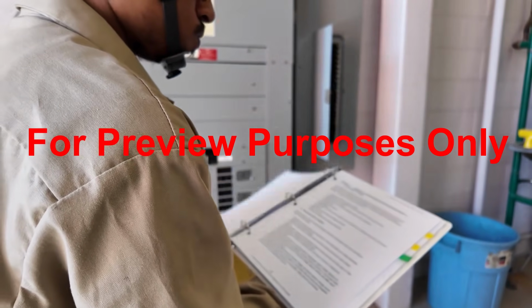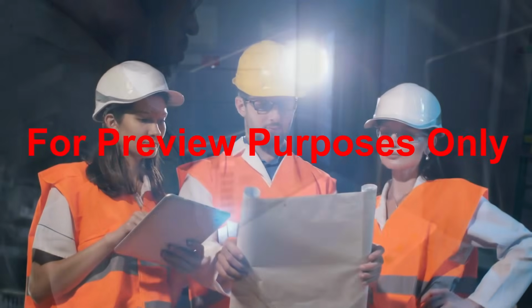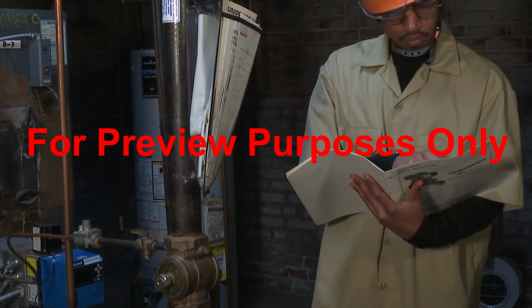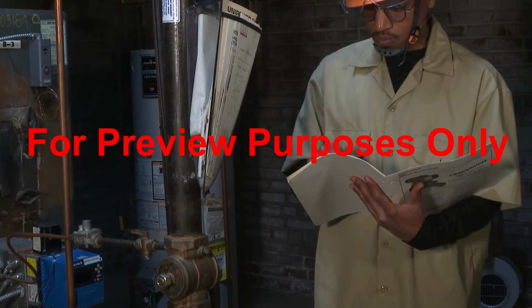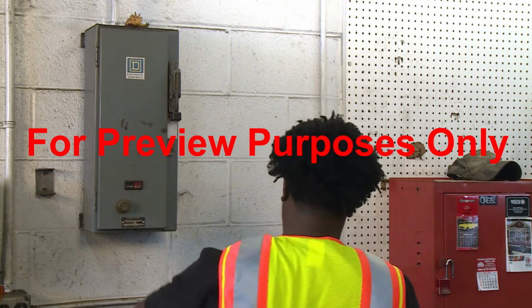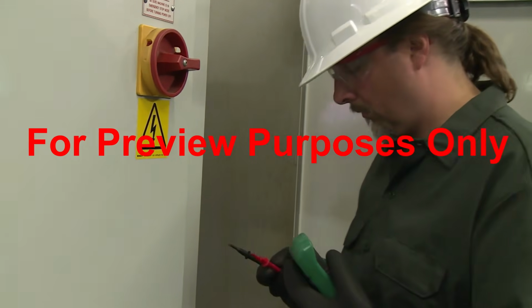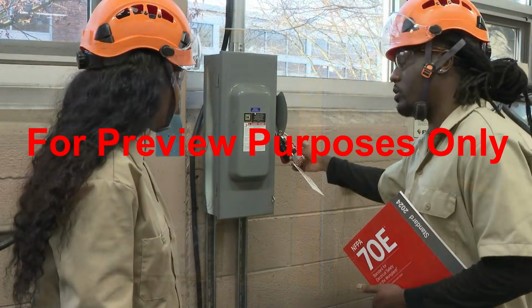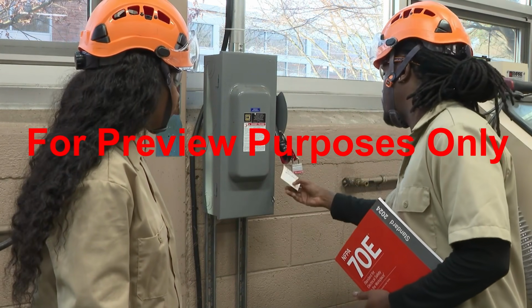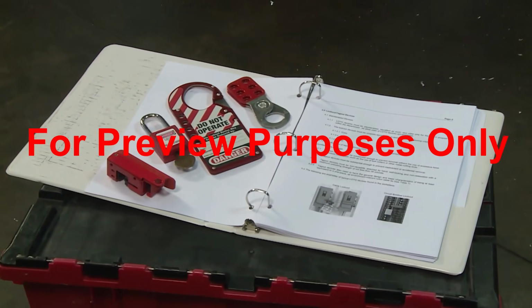So what specific steps should you take to create an electrically safe work condition for a task that you're working on? First, use any drawings, diagrams, and identification tags that are available to determine all of the possible sources of electrical supply to the equipment that you're working with. Next, interrupt the electrical current and open the disconnecting devices for each source of electrical supply. Then release any stored electrical energy. This could be as simple as flipping a switch or unplugging a power cord. After that, you should block or relieve any non-electrical stored energy to ensure that circuit cannot be accidentally re-energized. Finally, you should follow your job site's written procedures for applying lockout and tagout devices.